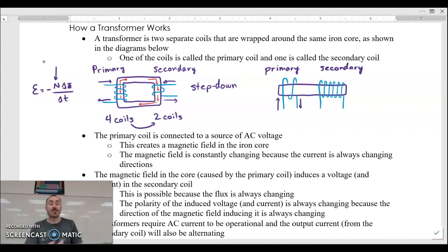In this case, this one would be called a step-up transformer because it has more coils on the secondary side. The primary side has 2 coils, the secondary side has 1, 2, 3, 4, 5, 6 coils. So the amount of voltage you get on the secondary side will be 3 times the amount you got on the primary side. This would be a step-up transformer.